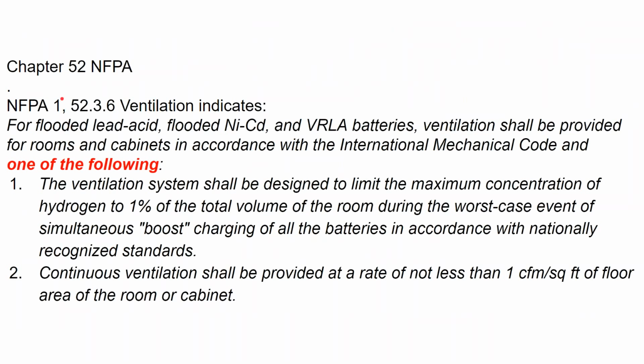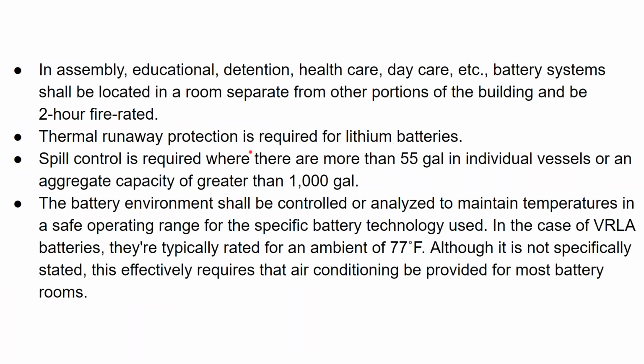Now the NFPA is a little bit more lenient than International Fire Code. NFPA lets you do either or. You can either have continuous ventilation or non-continuous ventilation that is still designed to limit the hydrogen in your room. So putting your batteries in an air-conditioned room can meet NFPA without continuous ventilation. Still probably a good idea to have that continuous ventilation in there. There are additional battery requirements in code for more critical buildings, where there's small children.